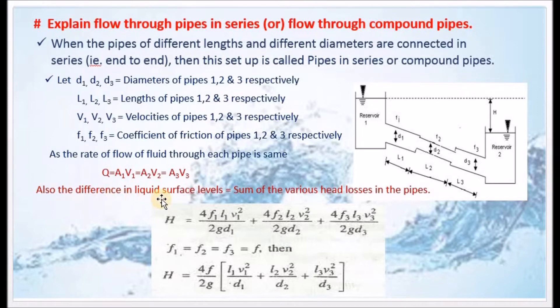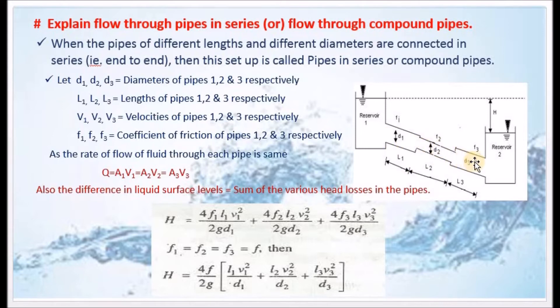Also, the difference in liquid surface levels is equal to the sum of the various head losses in the pipes. The liquid surface level difference represents the pressure head drop. The pressure head drop equals the friction head loss — summed across the first pipe, second pipe, and third pipe. The friction head loss for each pipe is 4F·L·V² divided by 2g·D.